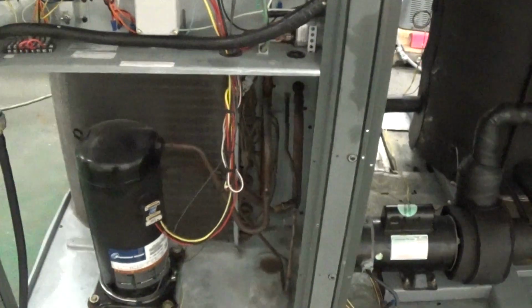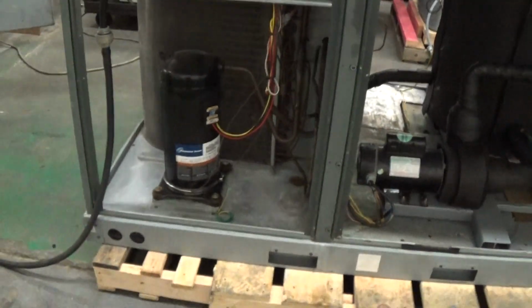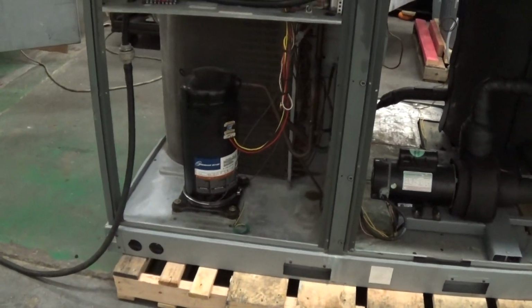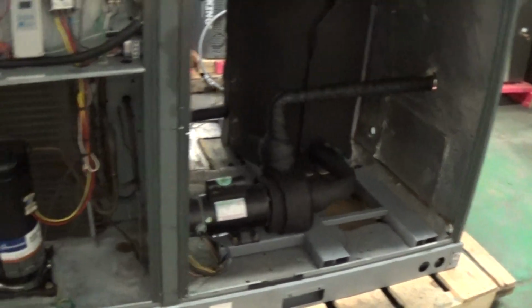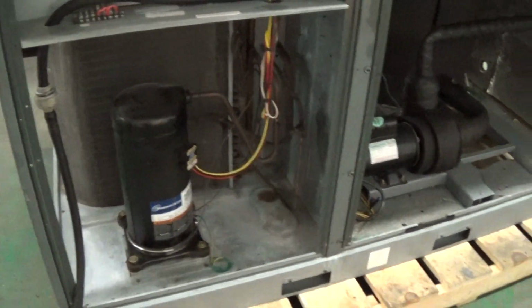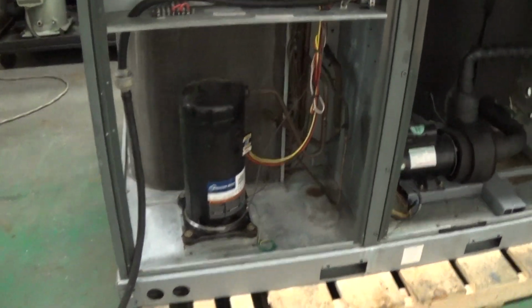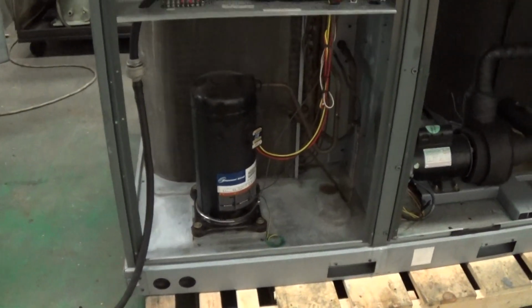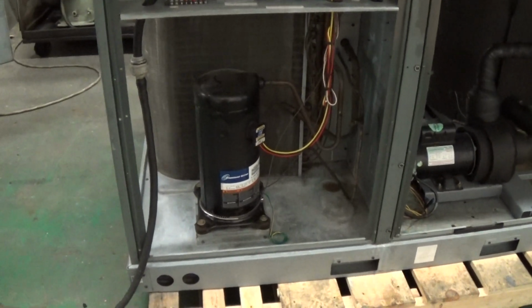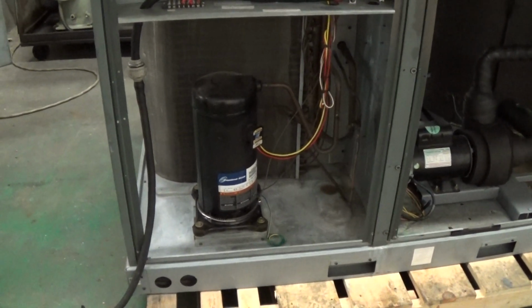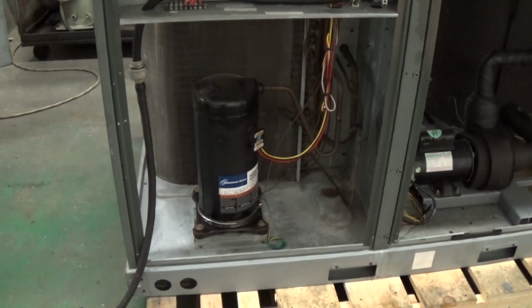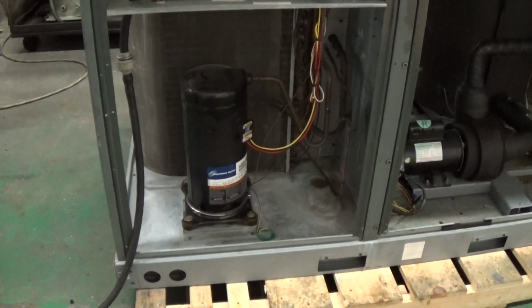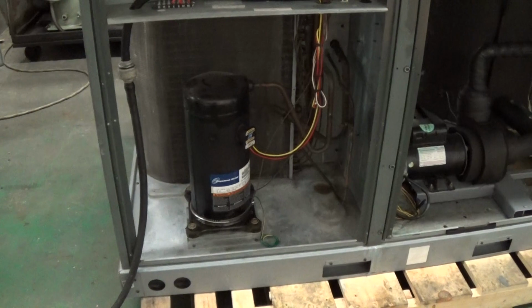Now when you first connect and start up a chiller, the thing about these chillers is they're 3-phase. The pumps and the fan are single-phase, so you can't go off pump rotation when you first power it up. And even when the compressor is rotating backwards, which is very bad if it does for a period of time, it's actually fairly quiet. So what I like to do, well, if you have a set of gauges there, an HVAC tech, it's a non-issue.